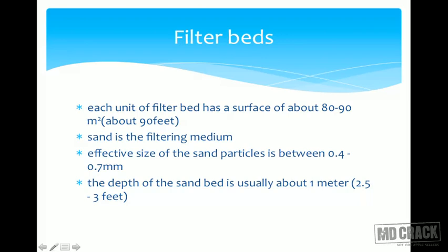Sand is the filtering medium here also. The effective size of the sand particles is between 0.4 to 0.7 mm. In the slow sand filter it was 0.2 to 0.3 mm, and here it is 0.4 to 0.7 mm. Therefore the diameter of the sand is larger and hence filtration is faster.